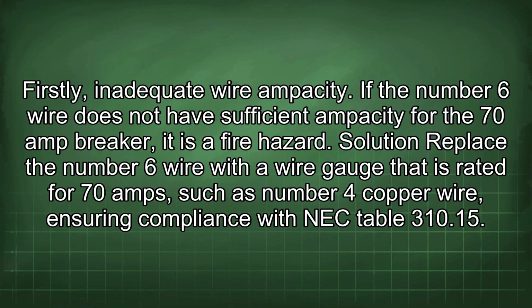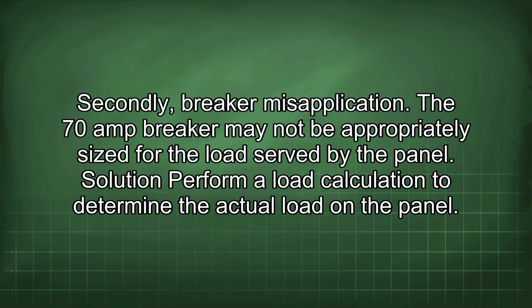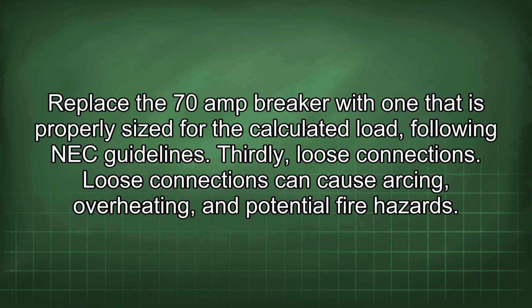Firstly, inadequate wire ampacity. If the number 6 wire does not have sufficient ampacity for the 70 amp breaker, it is a fire hazard. Solution: replace the number 6 wire with a wire gauge that is rated for 70 amps, such as number 4 copper wire, ensuring compliance with NEC Table 310.15. Secondly, breaker misapplication. The 70 amp breaker may not be appropriately sized for the loads served by the panel. Solution: perform a load calculation to determine the actual load on the panel. Replace the 70 amp breaker with one that is properly sized for the calculated load, following NEC guidelines.